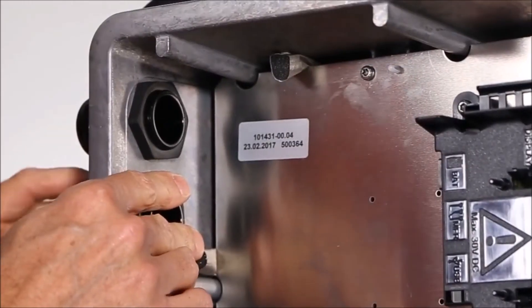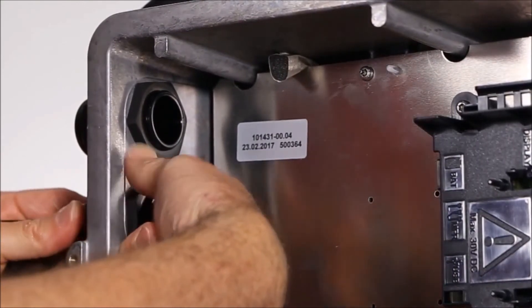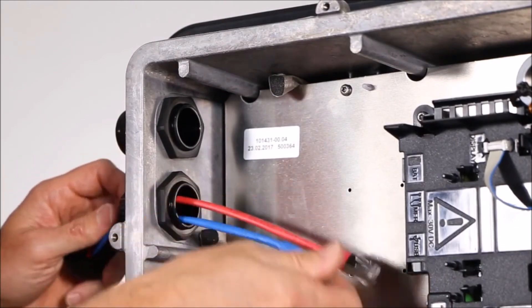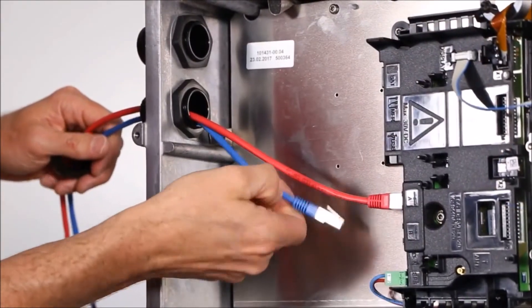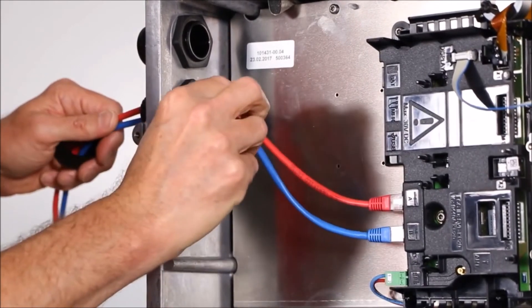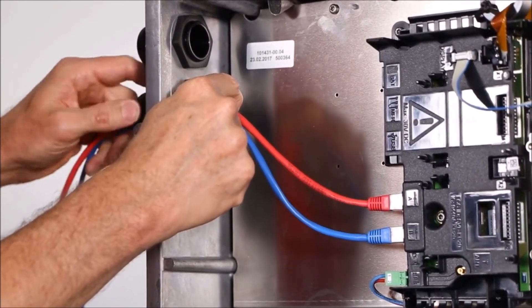For the communications, we bring the ethernet cable through one of the one-inch openings and connect it to one of the RJ45 ports on the communications board. Multiple inverter communication boards can be daisy-chained together using the second RJ45 port. When daisy-chaining, the ethernet cables can be up to 100 meters in length.